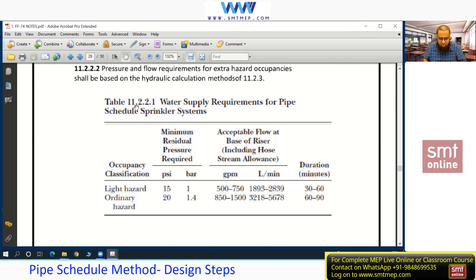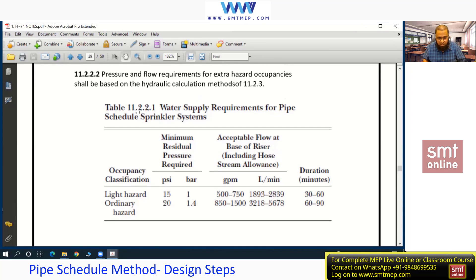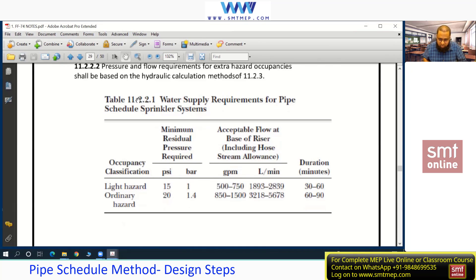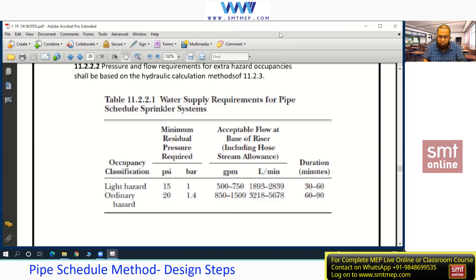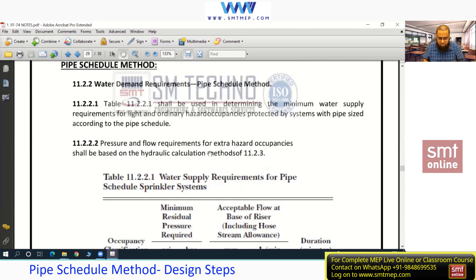You can highlight Table 11.2.2.1 in your hard copy — this is for the pipe schedule method. For the hydraulic method, we calculate both the residual pressure and the total pressure, which is the inflow node pressure — we'll discuss what inflow node means later. In the hydraulic method, the condition is that the pressure cannot be less than 7 psi.